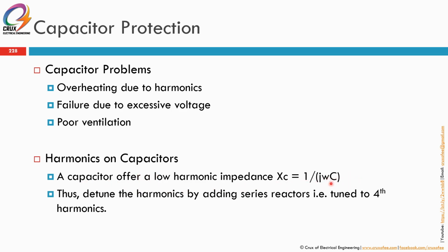If you can see, let's say in the system you have a lot of 12 pulse VSDs. The 12 pulse drives normally produce a lot of high 11th and 13th harmonics. If you initially had tuned your capacitor banks to the 11th harmonic, which is 11 times 50 hertz, about 550 hertz, and you input 550 hertz here, Xc will become almost zero. It is as if your capacitor is going to short circuit, so your capacitor will become a sink to these harmonic currents.